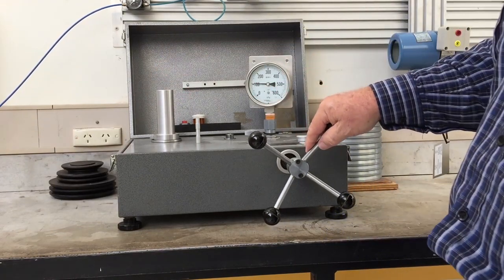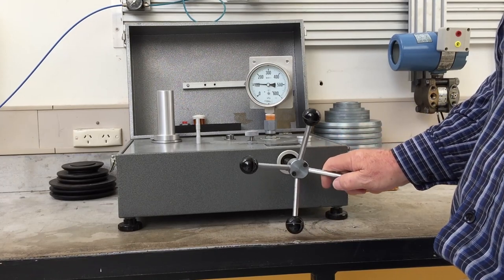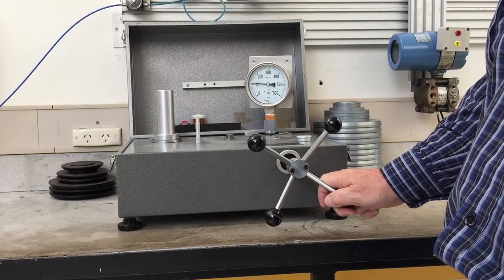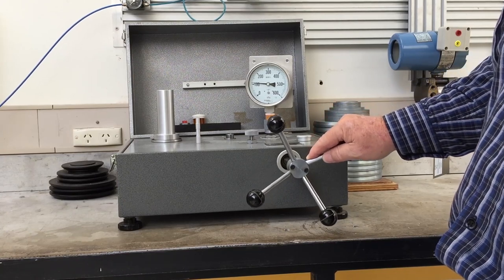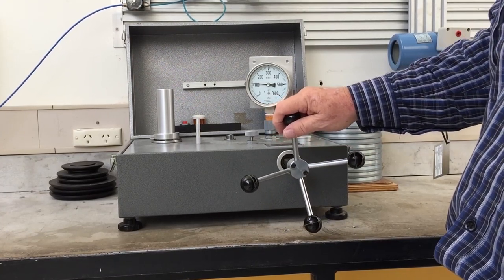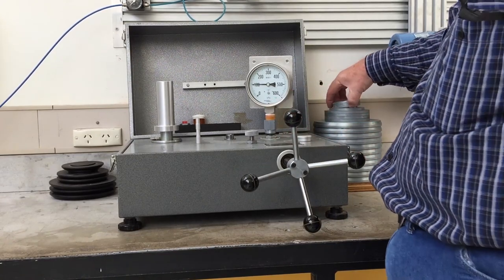Sometimes the piston adheres to its seat and the weight can be rotated to overcome any stiction. The first pressure is 100 kPa. Record the pressure indicated on the gauge.